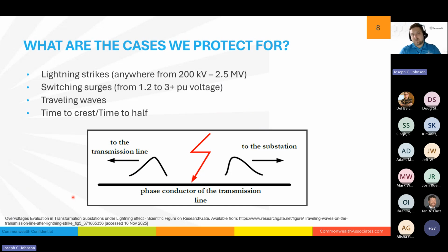These are traveling waves. So a traveling wave is basically created when a lightning strike or switching surge happens because there is a very rapid change in current across an impedance over a short amount of time. When a lightning strike happens, you're getting a very large amount of current injected into your line across an impedance, so very large voltage spike.